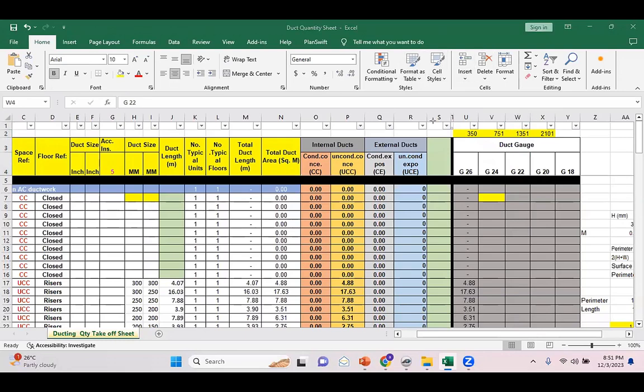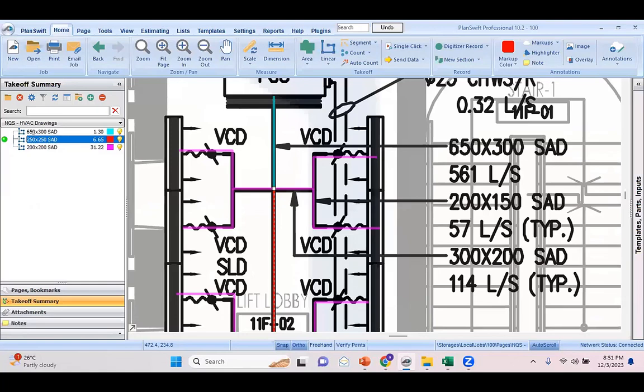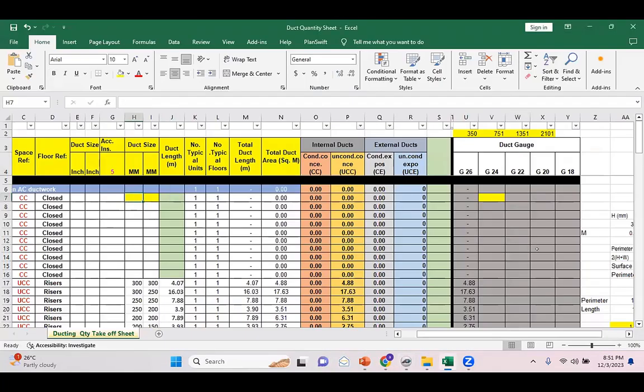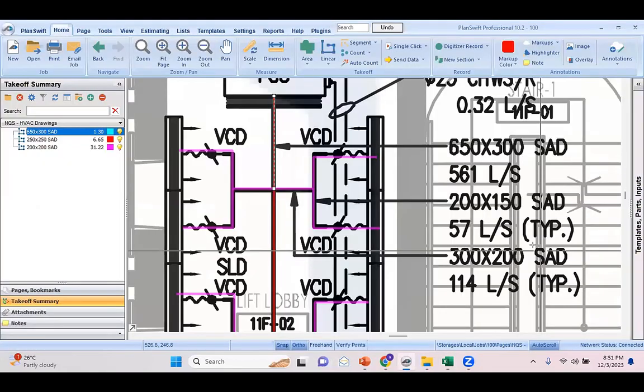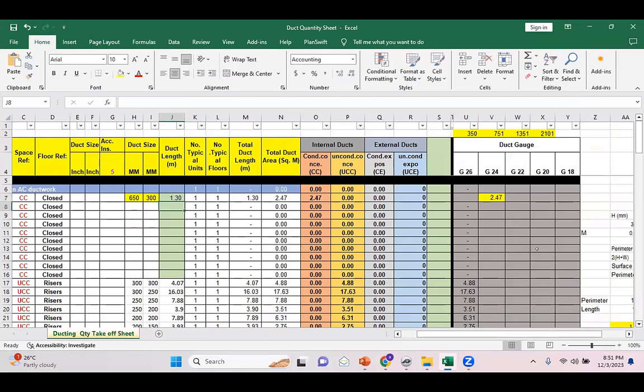Let's quickly go to my sheet. The size I have here is 650 by 300, so I'll put 650 and 300 as the two sizes, and the length of this duct is 1.3. Once I put that length, you can see it gives 2.47 square meters of duct, which is 24 gauge.